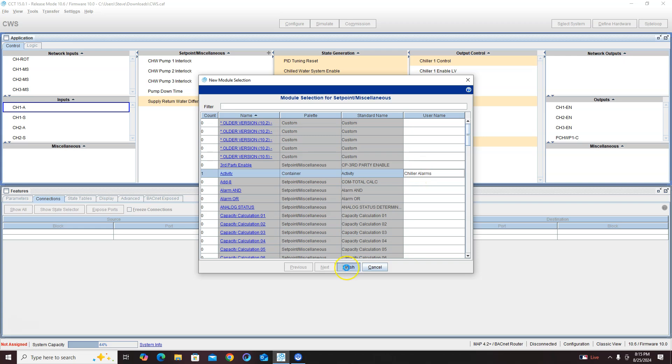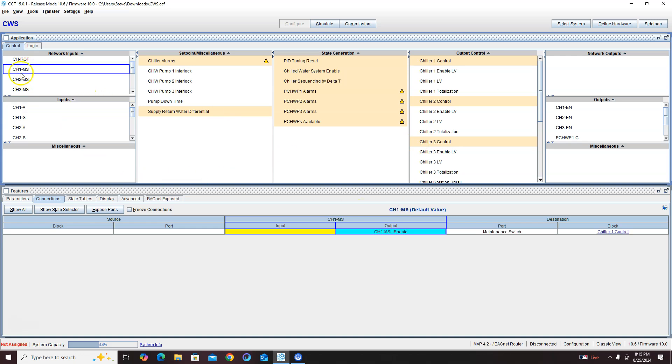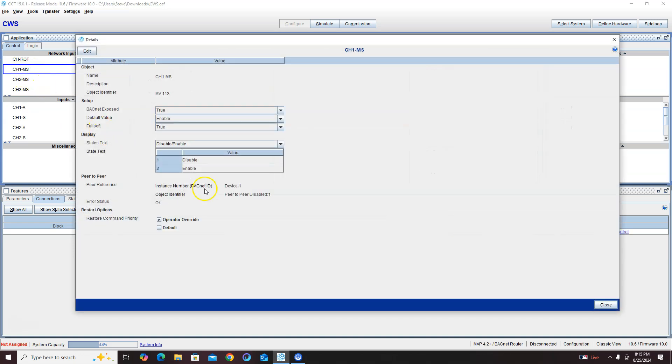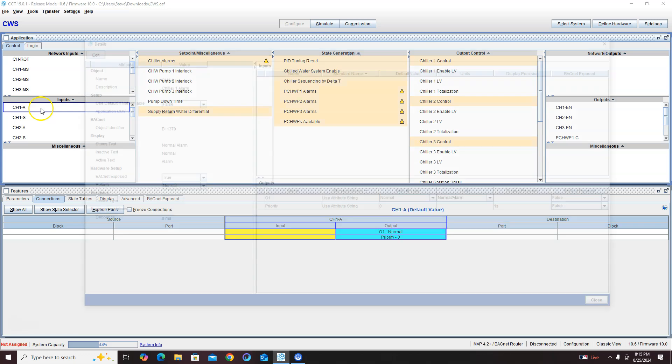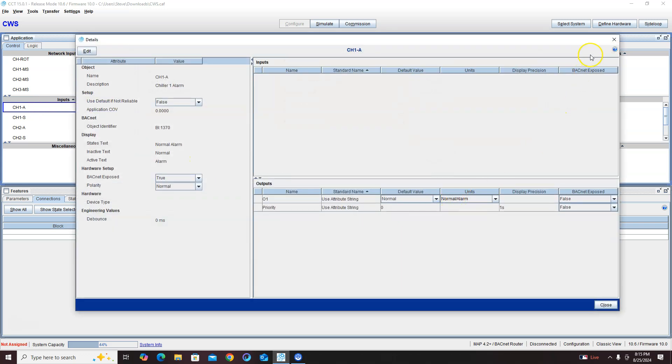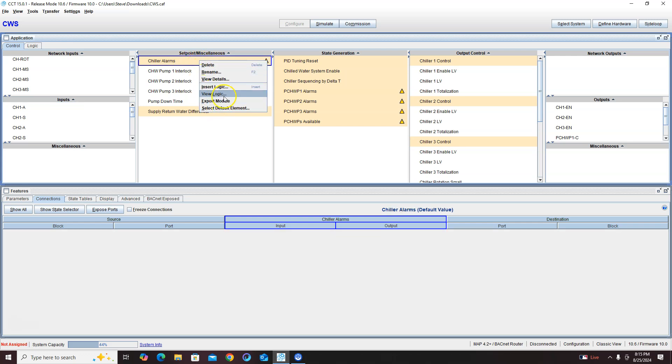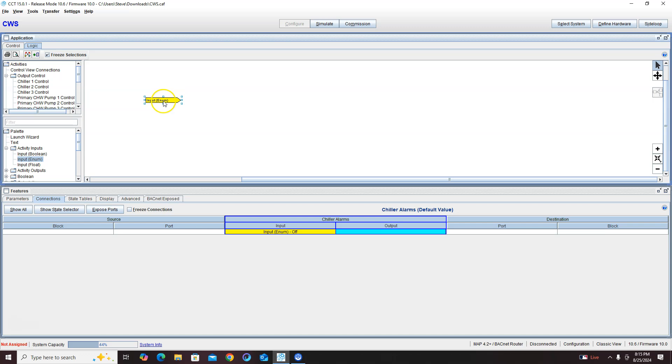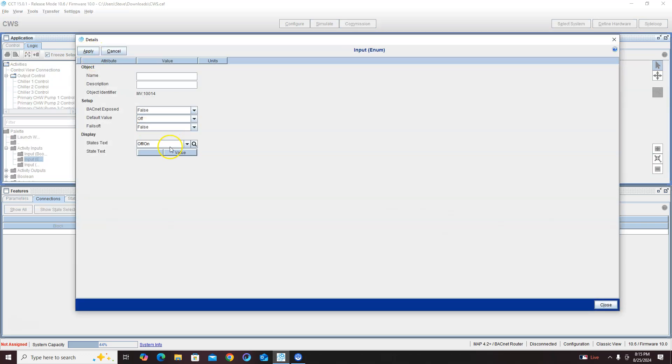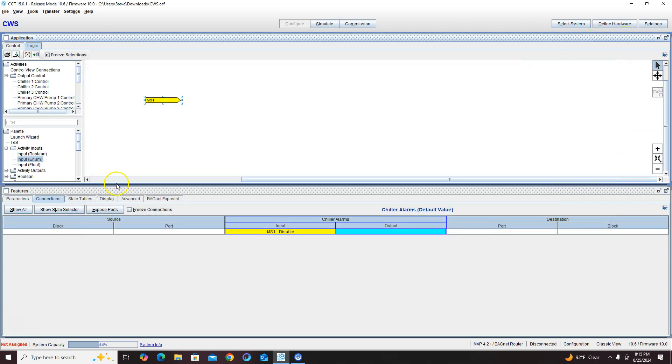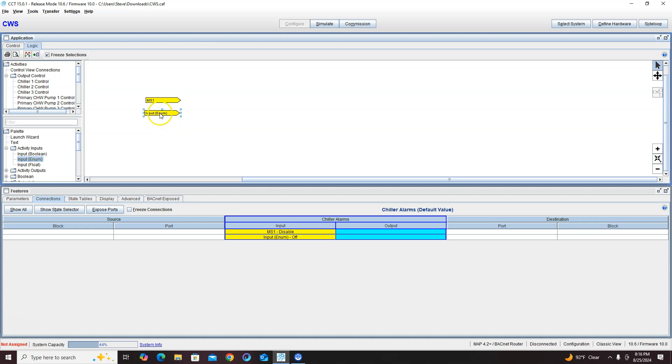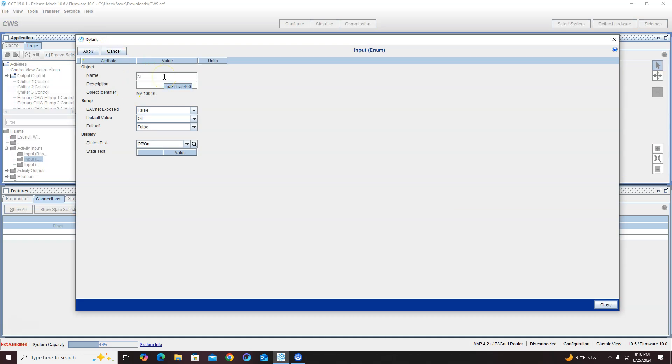Now the maintenance switch, the enum on this is disabled slash enable, and the enum on this is normal alarm. So I need to combine those two enums which isn't a problem. So we come in here to view logic and I know I'm gonna need an enum, and this one's gonna be let's say the maintenance switch - so this is a disable enable and we don't want the one with the space, we want the one with the slash. I want to call this ms one for maintenance switch one.